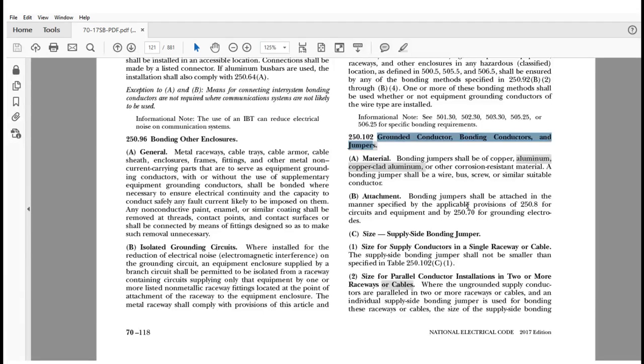It kind of removed the use of the 250.66 for these applications because at that point it was limited only to the 3/0 or 250 is the max, I believe, for the grounding electrode conductor. And it had nothing to do with the grounding conductor and the bonding conductors, and you had to use it, and then you get into the notes, and it just became complicated. So everybody went to 250.102. It used to send you back to 250.66 for sizing.